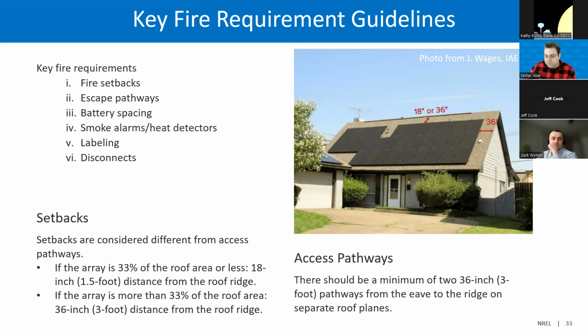different from access pathways. As an example, if an array is 33% of the roof area or less, 18 inches, 1.5 feet distance from the roof ridge should be available for access. And if the array is more than 33% of the roof area, 36 inches, like 3 feet distance, should be available from the roof ridge. And there should be a minimum of two 36-inch, 3-foot pathways from the eave to the ridge, on separate roof planes, which will give easy access for firefighters.